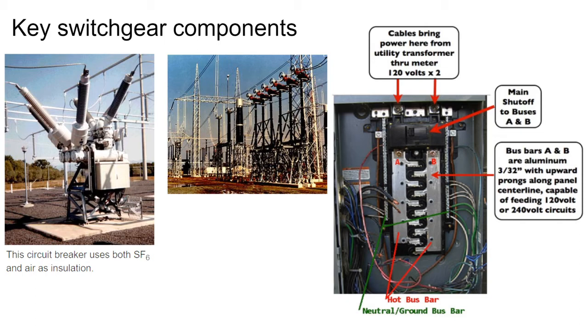Regardless of whether it's top-fed or bottom-fed, on a disconnect switch you have the option of which side to land the utility side on. Utility side is always coming in from the top, unless it's a bottom-fed service panel specifically. But like a knife switch disconnect panel, the utility side should come in from the top.